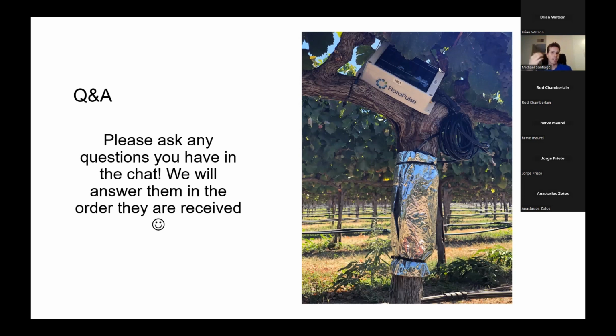When you're testing the sensor in the lab, you're looking at a few different things, as covered in the manual. First, you check that the sensor has a stable response—at least when it's in water, it should be measuring 0 relatively consistently.